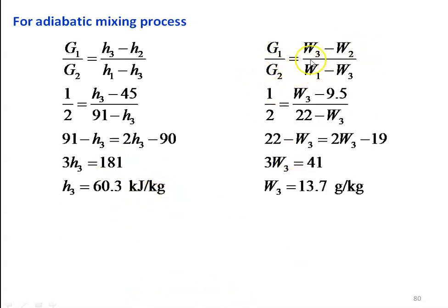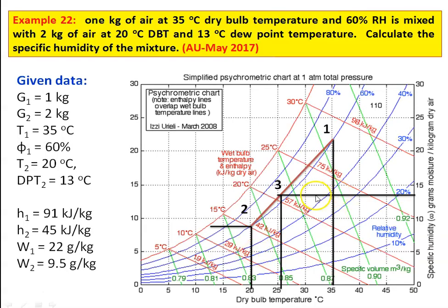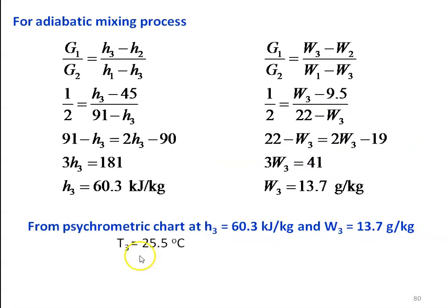Similarly, for specific humidity: G1/G2 = (W3 − W2) / (W1 − W3). Substituting known values: 1/2 = (W3 − 9.5) / (22 − W3). Cross-multiplying: 22 − W3 = 2W3 − 19. Rearranging: 3W3 = 41, so W3 = 13.7 g/kg. Using this value, go back to the psychrometric chart, locate point 3, and find the temperature, which is 25.5°C. Using the psychrometric chart is very easy to solve the problem; otherwise you have to remember all the equations. The important thing is to carefully locate and accurately read values from the chart.